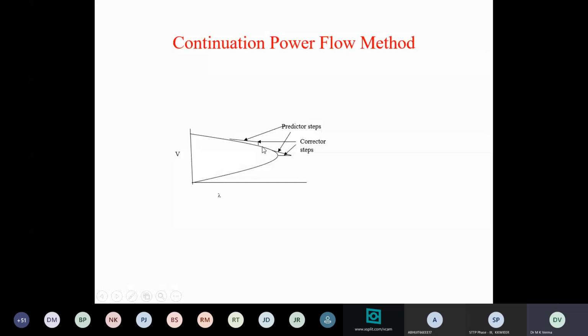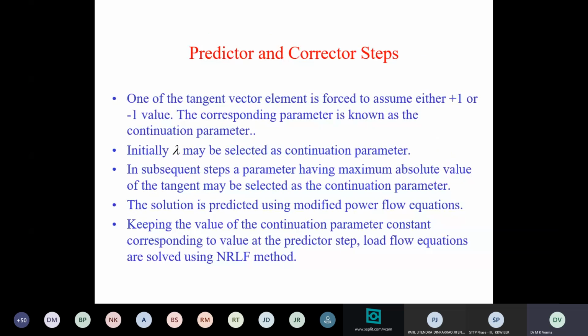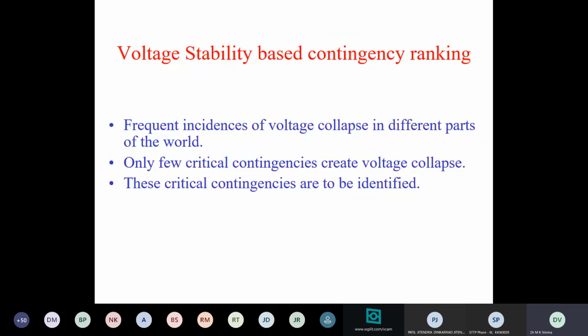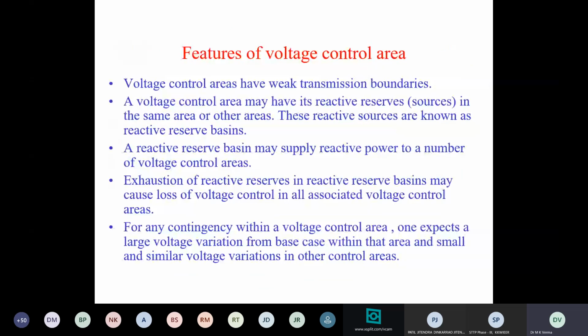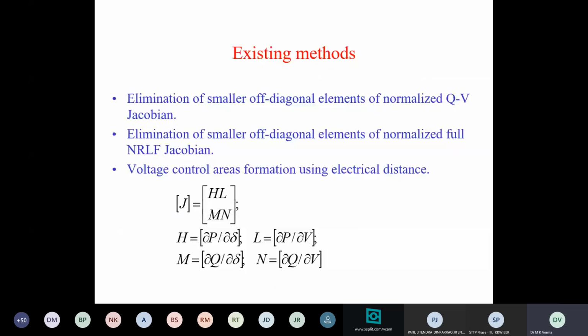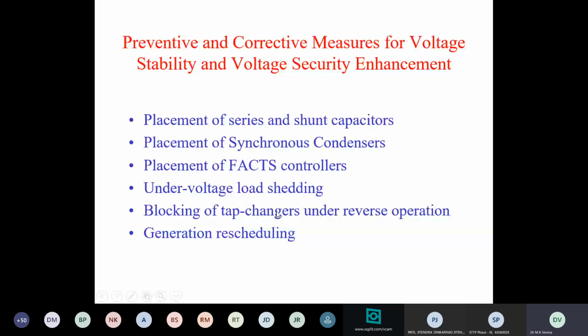Now what do you have to do? If you see that load is high and voltage has gone beyond a certain lower limit, the under voltage limit, you do under voltage load shedding. If voltage goes below certain acceptable limits, you can do under voltage load shedding. But this is the worst option, which irritates consumers. But if you have no other option left, then you can go for under voltage load shedding to prevent the system from voltage failures. Next is blocking of tap changers under reverse operation. I told you that reverse operation may cause voltage instability, so you block tap changer operation in reverse operation. Then generation rescheduling: you can have optimal reactive power dispatch, and the optimal reactive power dispatch may be done based on voltage stability criteria.